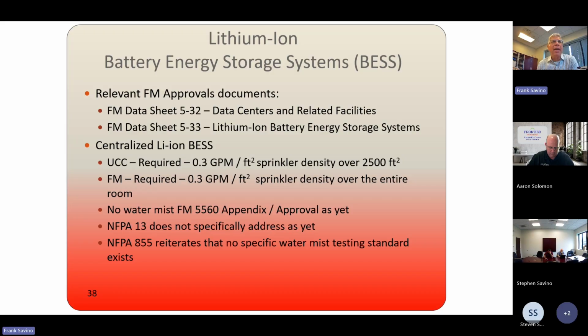So lithium ion energy storage systems. So again, the relevant documents, FM 5-32, 5-33. Now this, we're talking about here centralized lithium ion batteries. The Uniform Construction Code, which is adopted by most states, has a requirement of a 0.3 gallons per minute density over 2,500 square feet. Factory Mutual requirement is 0.3 over the entire room.